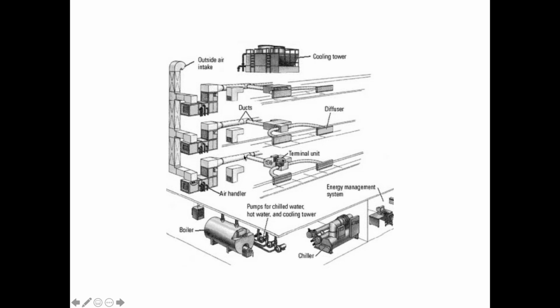The ducts go out through the floor, and they branch out into a main duct and then into trees, like branches, and so on and so forth, to all these diffusers. The ductwork gets smaller and smaller as it goes to each one of them. In some of these systems, the ductwork just goes out to the individual diffusers, right? And the individual diffusers all have the same amount of air coming out of them. And the fans on these systems run constantly. They just run all the time.